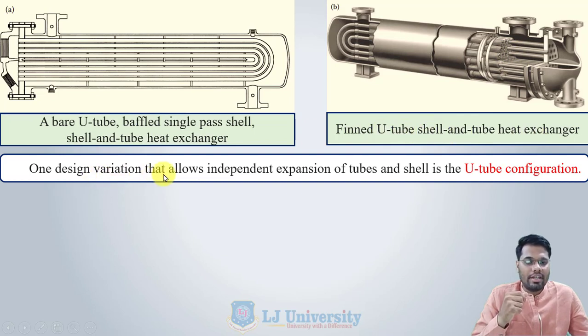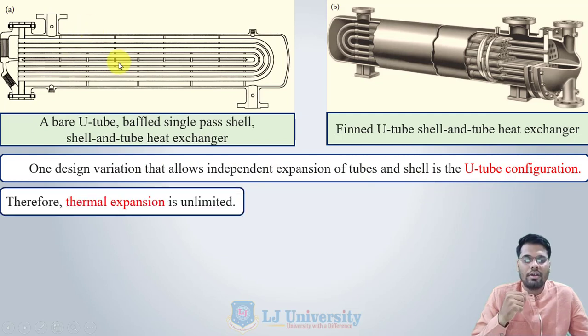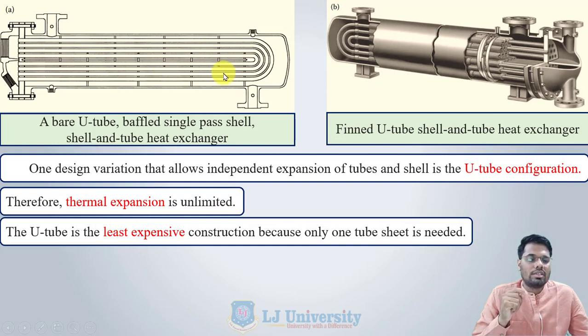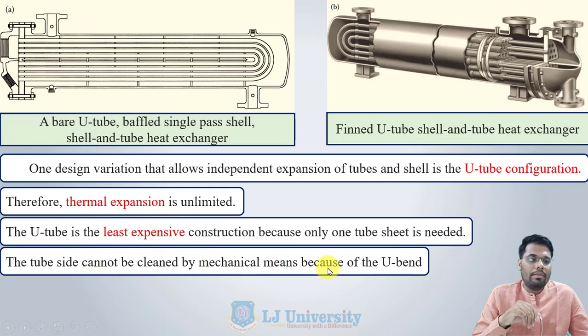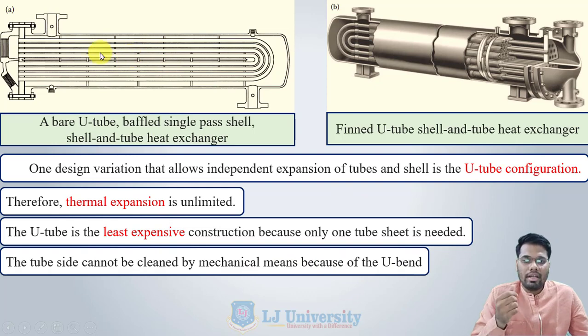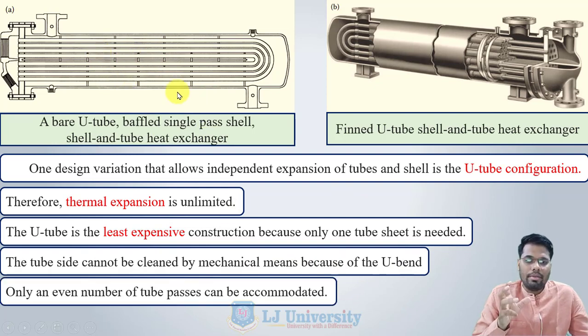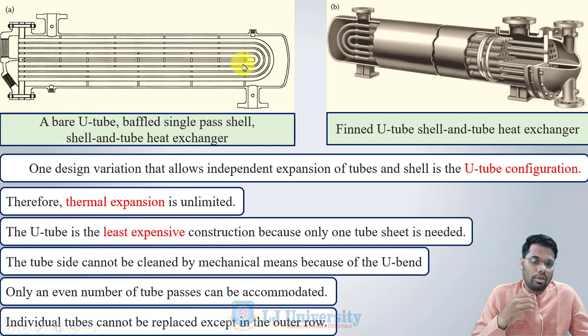One design variation that allows independent expansion of tubes and shell is the U-tube configuration, so thermal expansion is unlimited. The U-tube is the least expensive construction because only one tube sheet is needed to support all the tube bundles. However, the tube side cannot be cleaned by mechanical means because of the U-bend, only an even number of tubes can be attached, and individual tubes cannot be replaced — the whole bundle must be replaced.